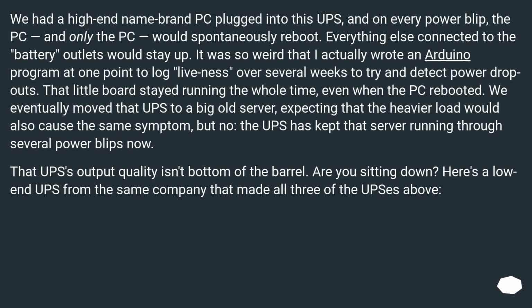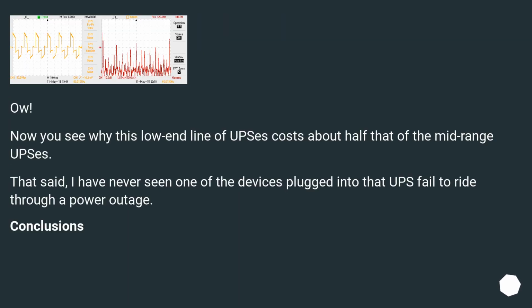That UPS's output quality isn't bottom of the barrel. Are you sitting down? Here's a low-end UPS from the same company that made all three of the UPSs above. Wow! Now you see why this low-end line of UPSes costs about half that of the mid-range UPSes. That said, I have never seen one of the devices plugged into that UPS fail to ride through a power outage. Conclusions.